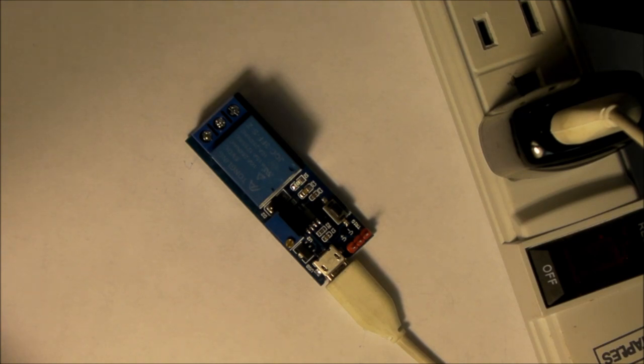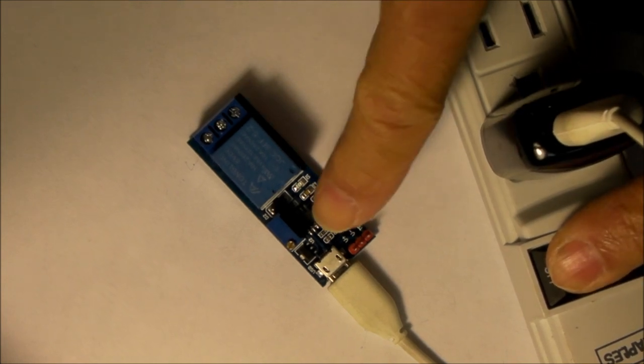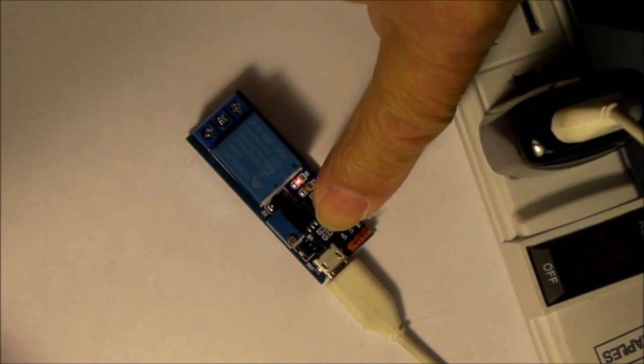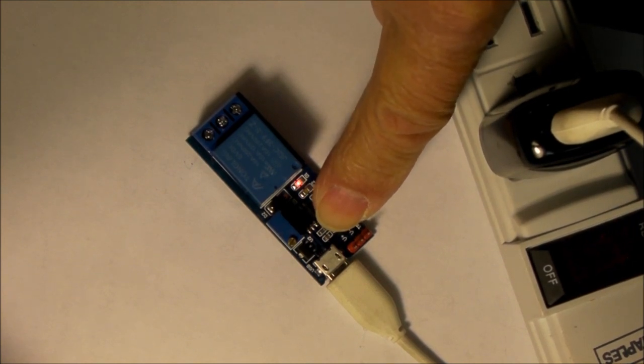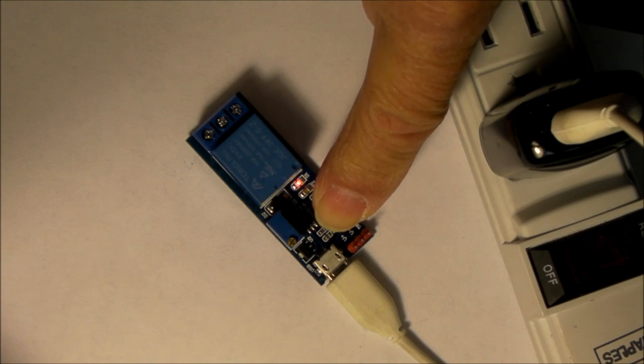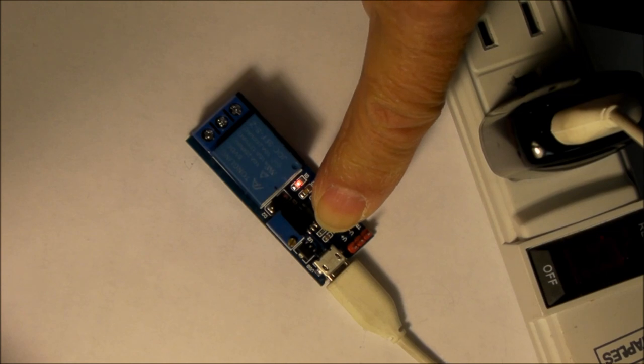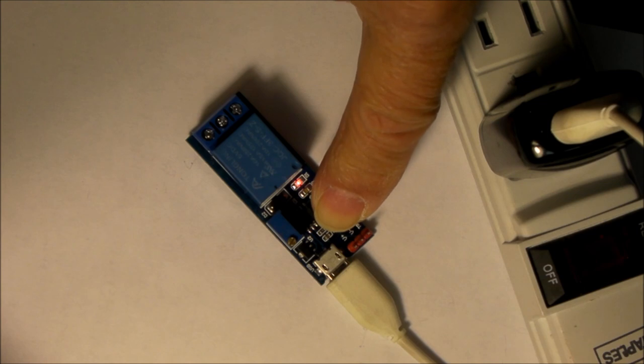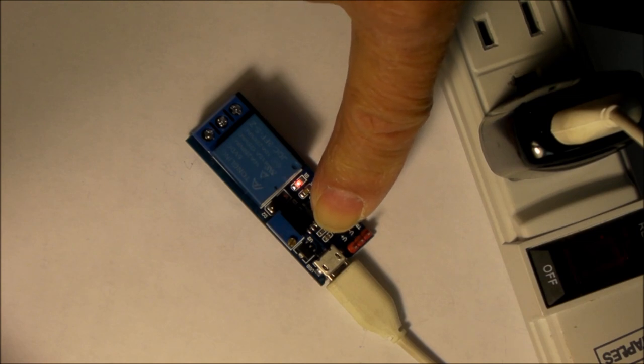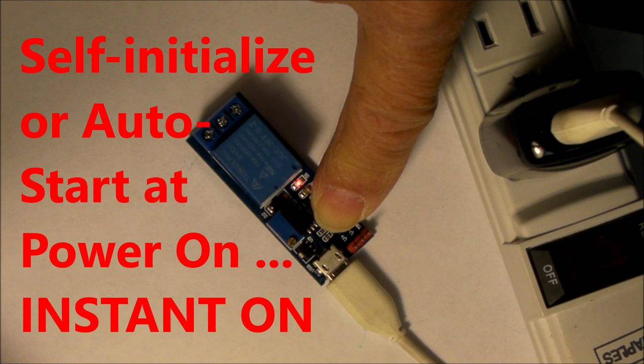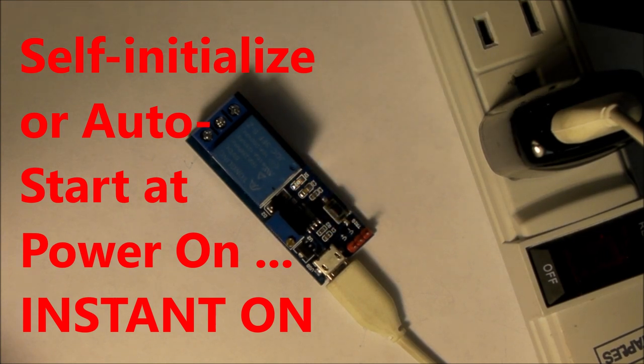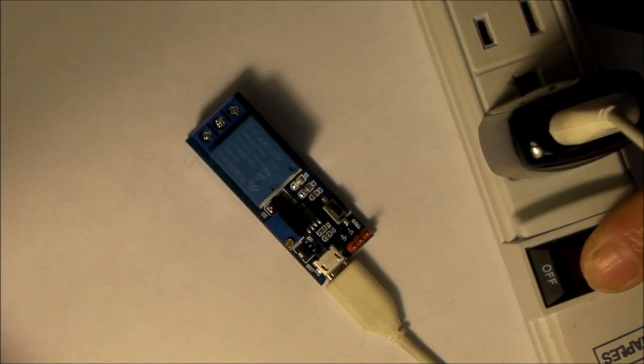So you can see here that if I were to remove the switch and just jumper it with a piece of wire, that would essentially be the same as this, and the timer would never expire. So therefore the relay would never open. The relay's closed right now. It would just stay closed because the switch is depressed. So shorting the switch out and or replacing it with a piece of wire was not going to accomplish what I needed to. But I have come up with a modification that allows the module to self-initialize or to auto-start upon application of power. And let me demonstrate that for you.